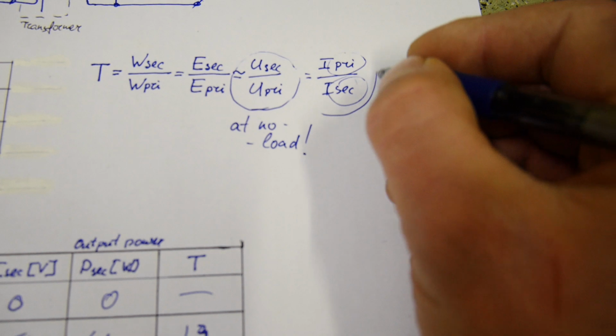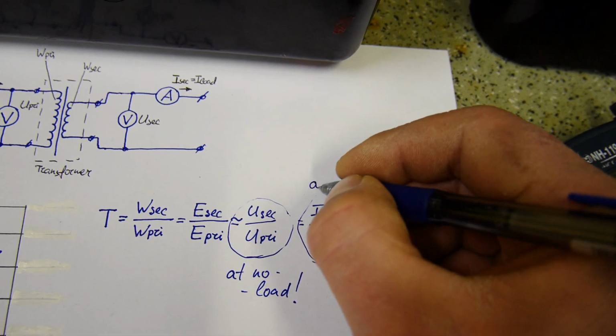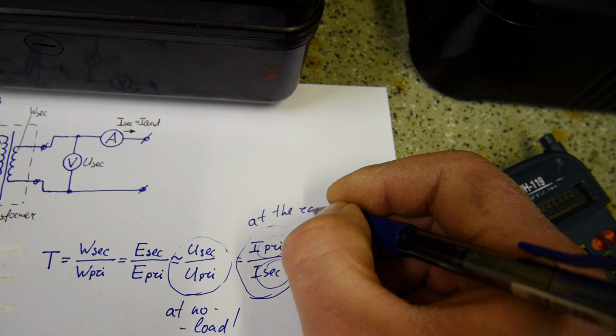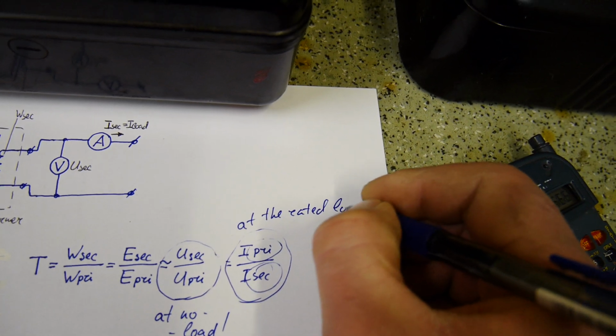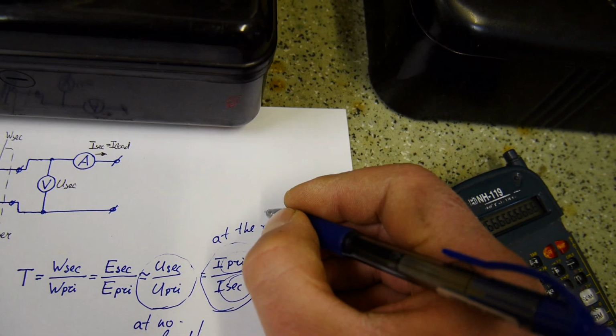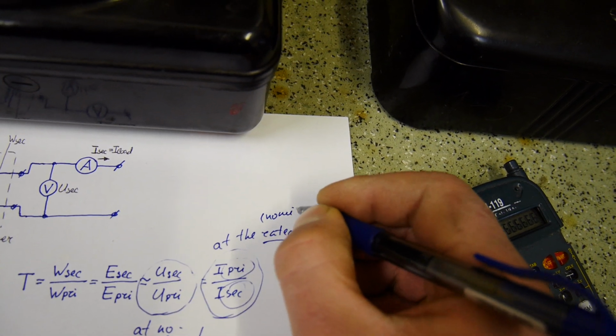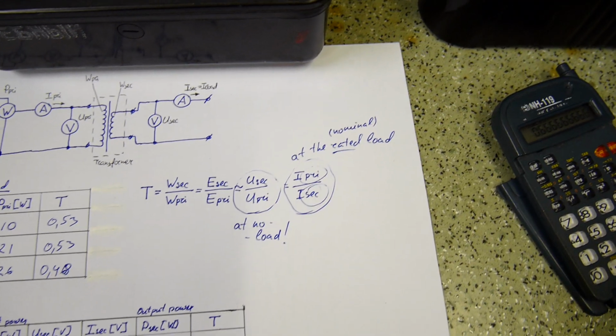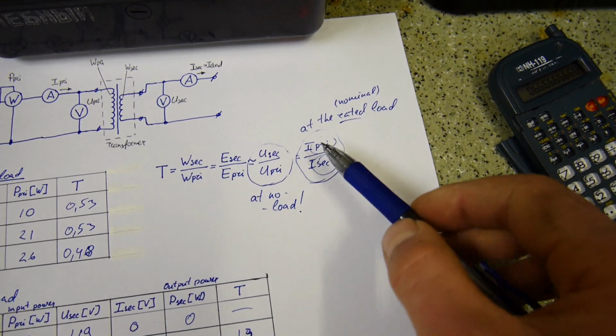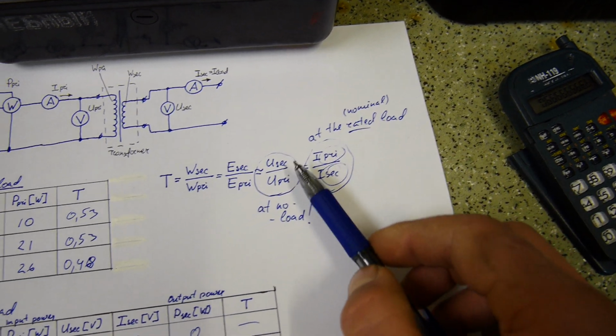So we have to continue to increase load current. We have to get these values which have not been measured because my rheostat heats too much. Yeah. So this approach can be used only at the rated load. Rated, also sometimes called nominal. So you have two possibilities how to measure turn ratio: by means of currents at the rated load or by means of voltages at no load.